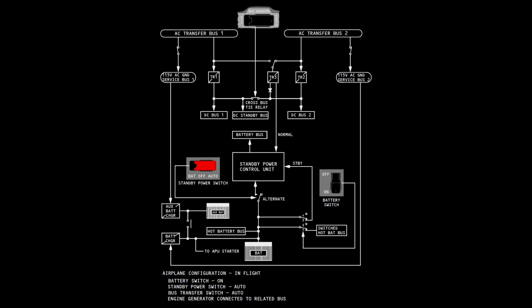Under normal conditions, DC bus 1, DC bus 2, and a DC standby bus are connected via the cross-bus tie relay. TR1 and TR2 are each powering DC bus 1, DC bus 2, and the DC standby bus, while TR3 powers the battery bus and is a backup power source for TR1 and TR2.